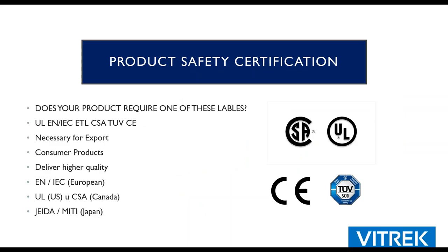All right, so here's the big question. Obviously, you see these labels all over the place: UL, CSA, CE, TUV, and there's a handful of others that we have listed. These will typically be on products, and there's going to be a 4-digit number next to them, and that verifies that the product has been tested to a very specific set of standards. You're going to have a 100-page standard that goes through the safety all over the place, from balance, weight, RF, all kinds of things. And there's going to be one section there that's electrical safety, and that's really the part that we specialize in. That is where you're going to have to use a Hipot tester to perform those tests.